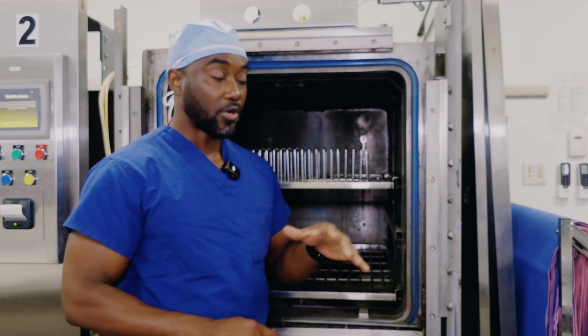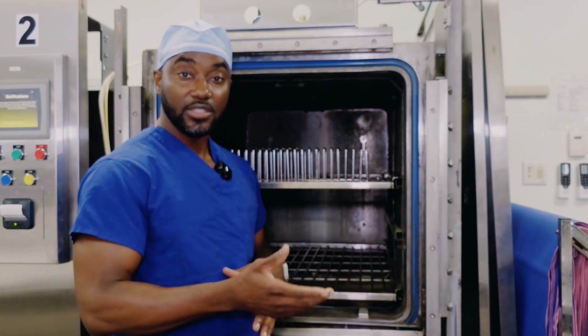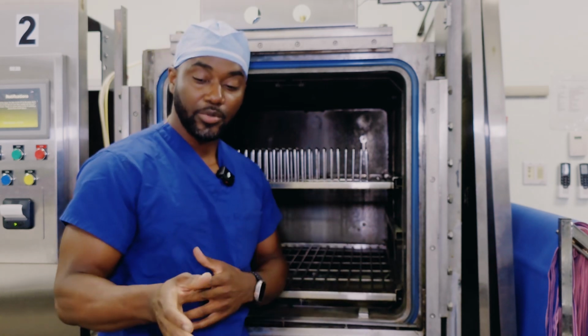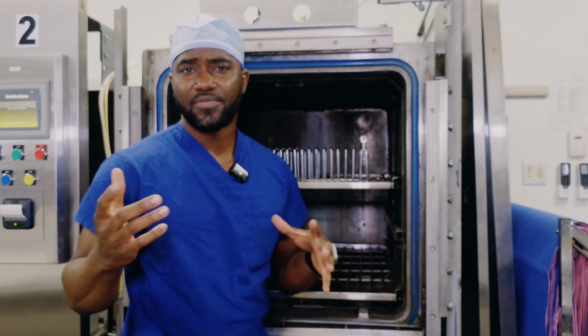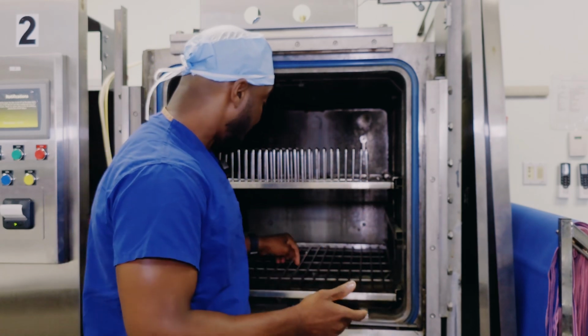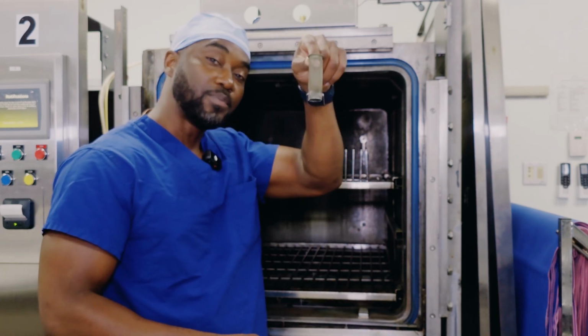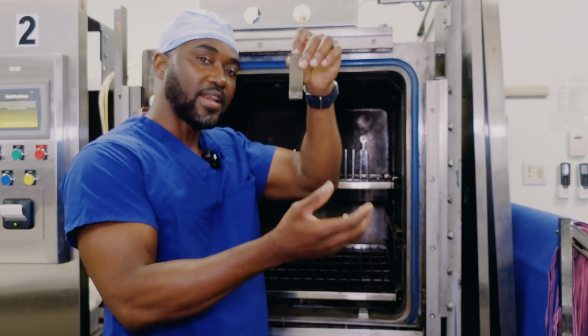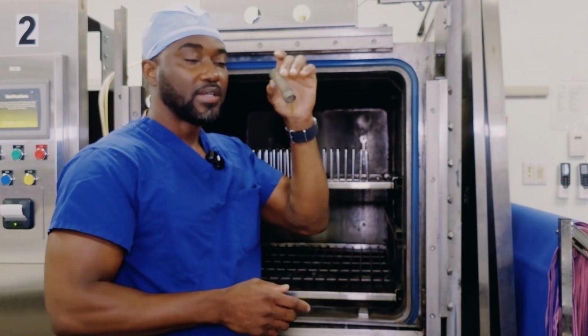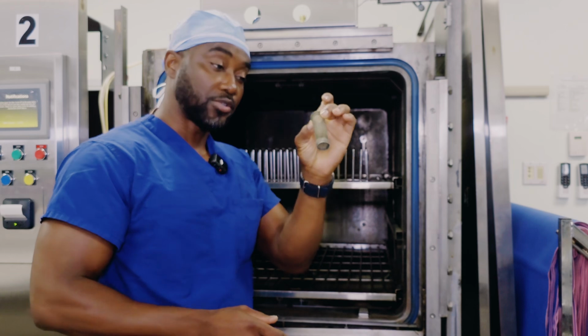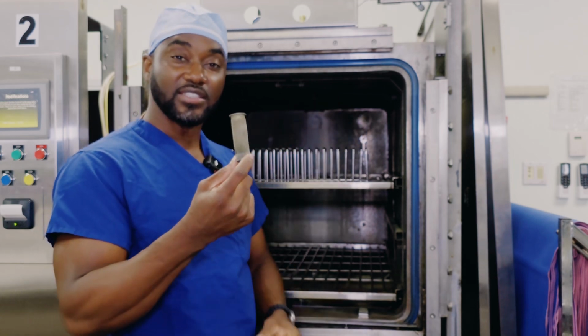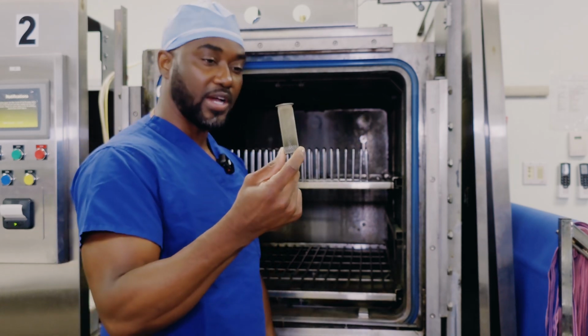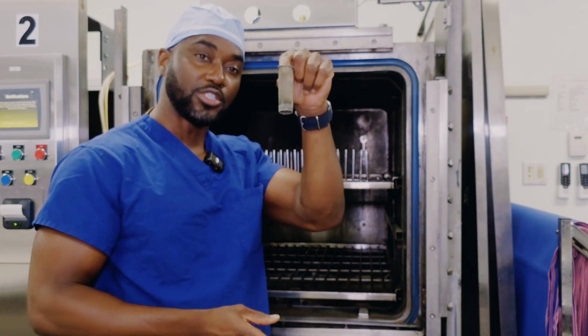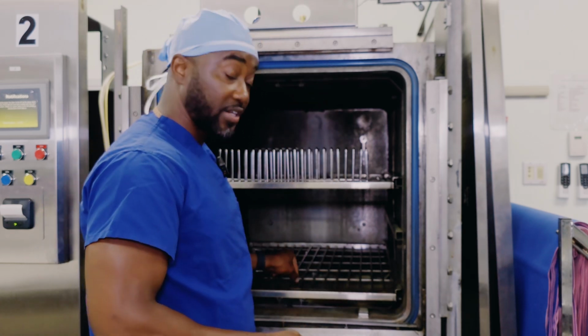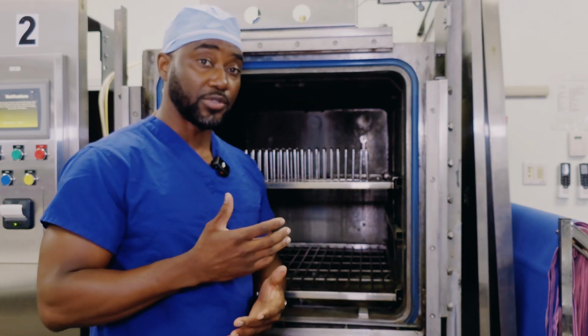The next step is to call your manager or supervisor. Let them know that air is not escaping and the Bowie-Dick test failed. There are a couple of factors affecting that. You might have a drain strainer that is clogged and not allowing air to properly escape. That's why you need to check your drain strainer on a daily basis, and my advice is to check it on every shift. If you work in a hospital, make sure you pull out the drain strainer to check it every shift or on a daily basis and make sure it's not clogged.